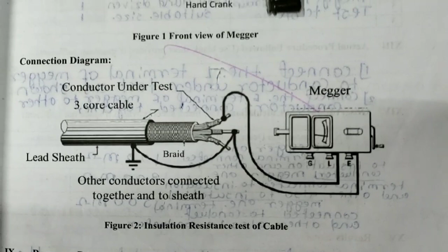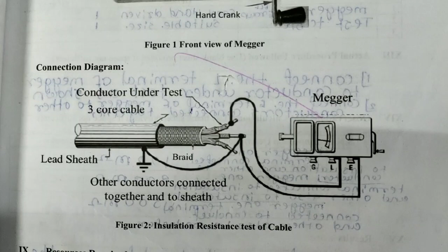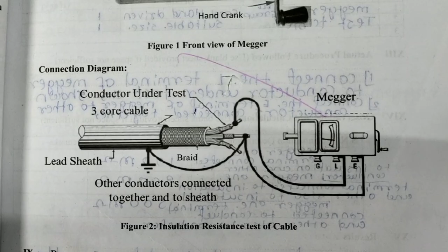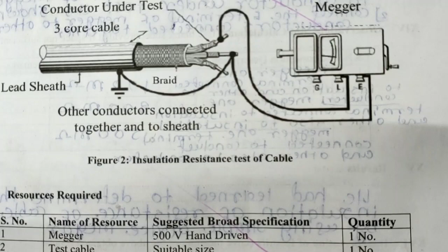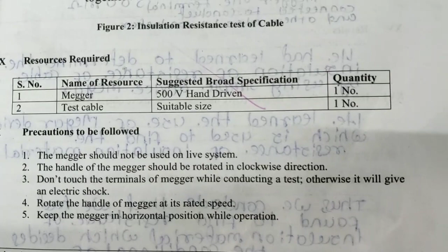A conductor is given there, a 3-core cable is given, and the Megger is connected across two wires to measure its resistance. So the Megger and cable are shown, then the other conductors are connected together in series. Okay, it is an insulation resistance test of cables. Now, resources required. If you want to perform this experiment, you will require these resources: Megger 500 volt hand driven, one number, and test cable of suitable size.